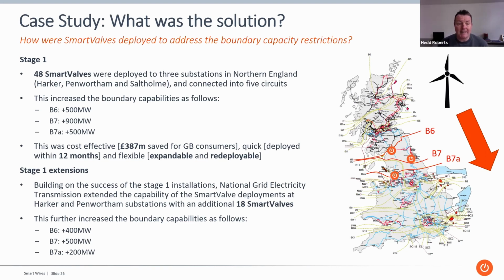The headline impact is a significant saving for GB consumers, 387 million, achieved very quickly. As mentioned, the key thing is the flexibility, expandability and redeployability of the devices - so much so that National Grid built on the success of those stage 1 installations with extensions at both Harker and Penwortham. Another 18 smart valve devices were deployed, further increasing boundary capacities by another 400 megawatts on B6, 500 on B7, and 200 on B7A - a significant increase again.